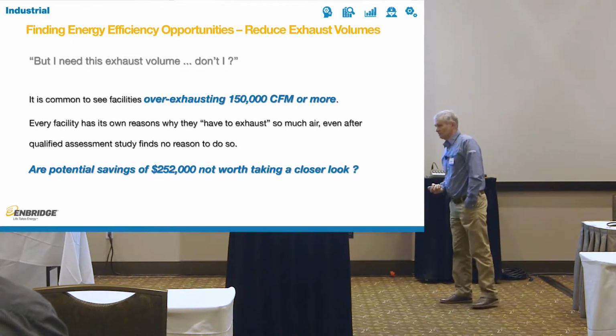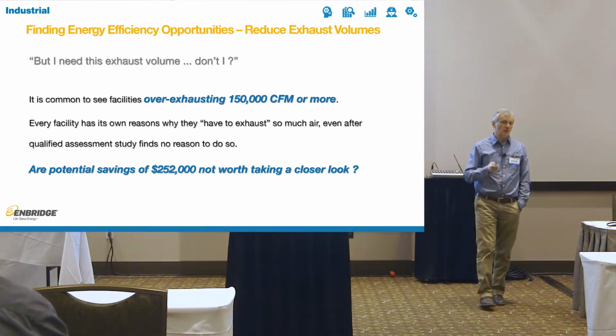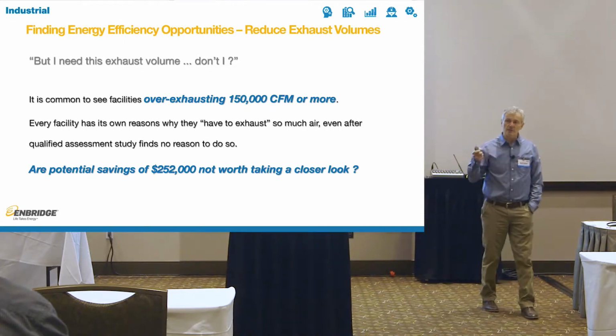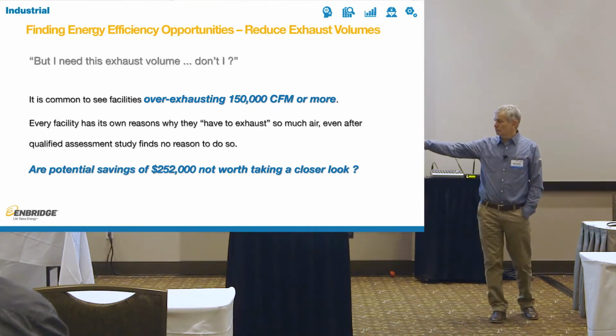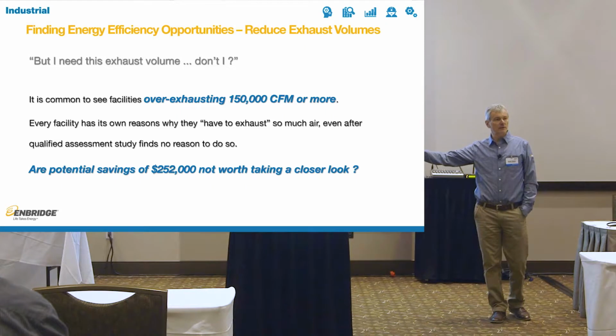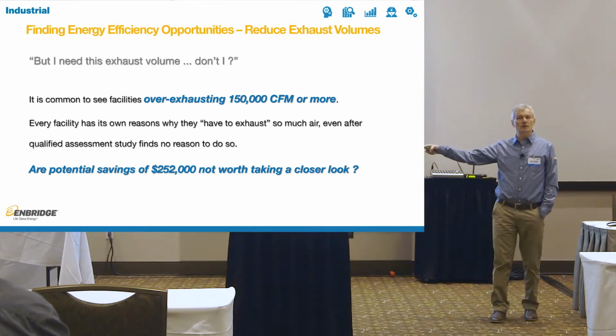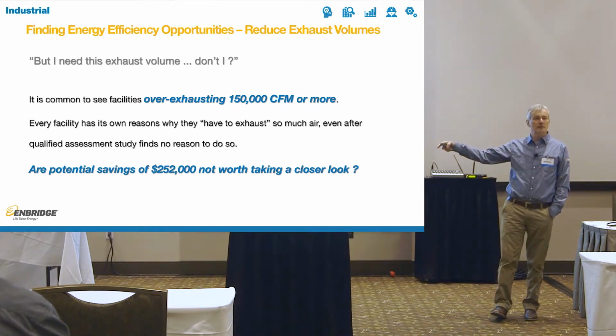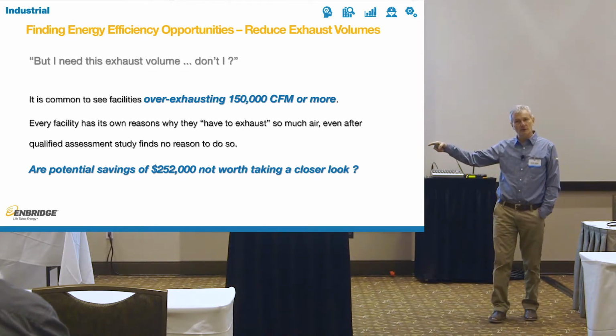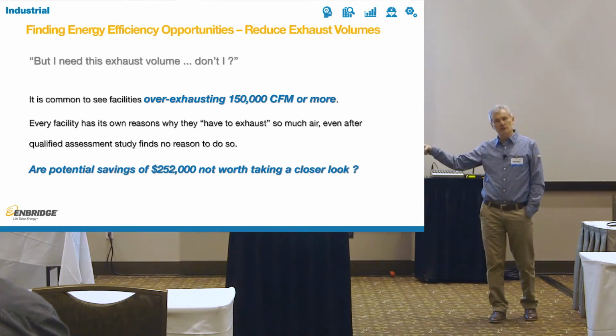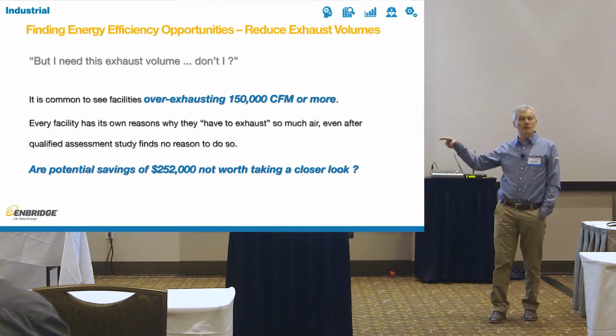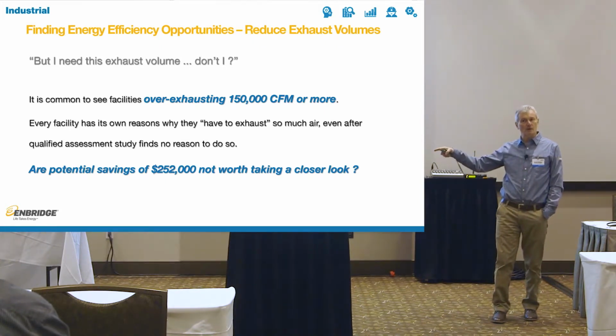And these are the potential savings, $252,000. Because when you turn off the 3 times exhaust volume, those exhausts, the fans themselves, are not taking just thermal energy out. They're also taking a lot of electricity out. I saved one facility in 2012 when I worked with them. By reducing their exhaust, they had 400,000 CFM of additional air that they didn't need. We turned it off. We saved them 1 megawatt of electrical power a year.